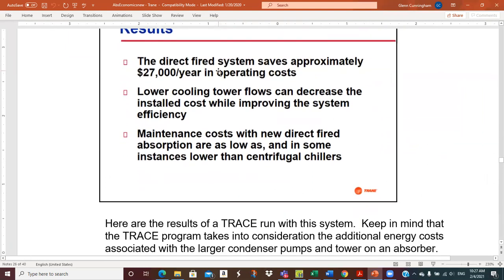The direct fired system saves approximately $27,000 per year in operating cost. So lower cooling tower flows can decrease installed cost while improving system efficiency. Okay, so there's a lot in that bullet point. It's not really obvious because, for our standard absorber, it's going to require more cooling tower flow.